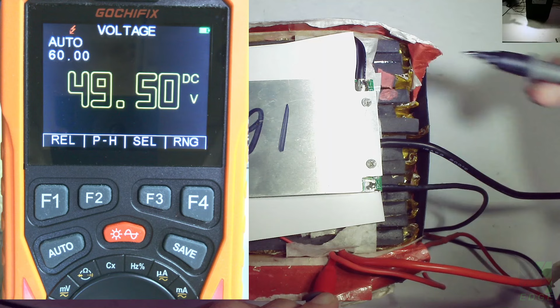You can see I'm getting a high voltage warning. It probably would zap me a little bit under some conditions. But as you can clearly see, this battery is reading at about 49.5 volts. However, that's actually pretty low. For a 16-cell lithium iron phosphate battery that hasn't been abused and run flat, it ought to be up in the 50 volt range, maybe 51 volts. As you can see, it's clearly not, it's 49.5 volts. Now that doesn't tell me a whole lot. It's useful information to know, but it still isn't going to help me solve the problem.